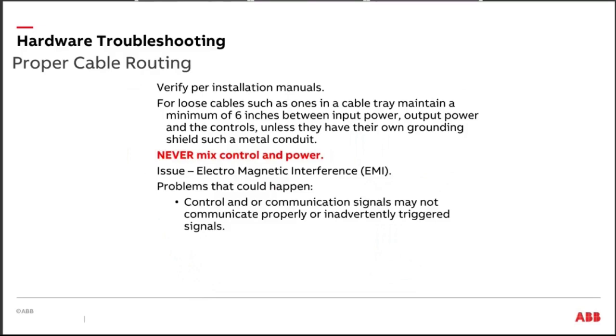If you're putting it in cable tray, make sure you're keeping good segregation on your motor leads. Make sure that you're mixing your motor leads correctly. Don't run all of A phase in one section and all of B phase in another section, and C phase or T3 in a third section. Never, ever, under any situation, mix control and power wire.